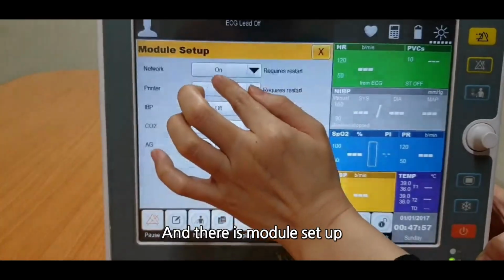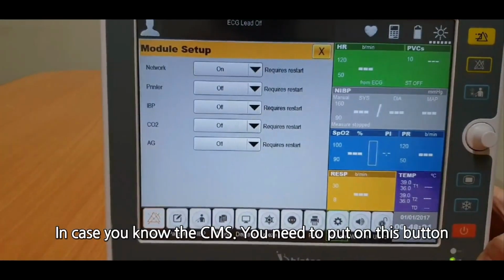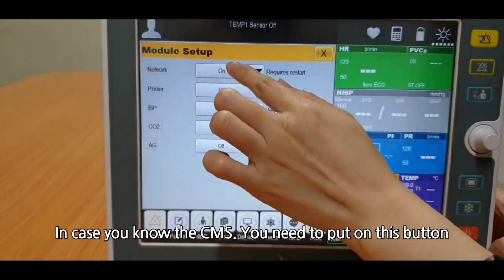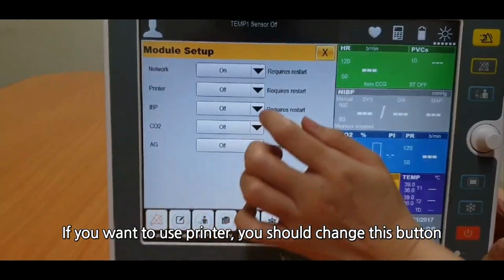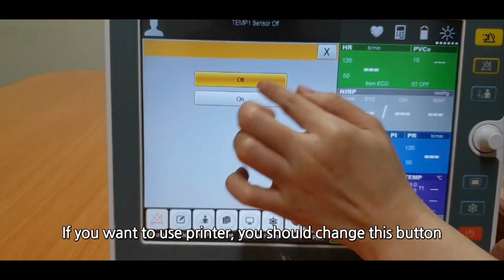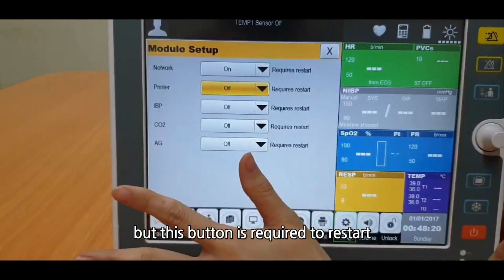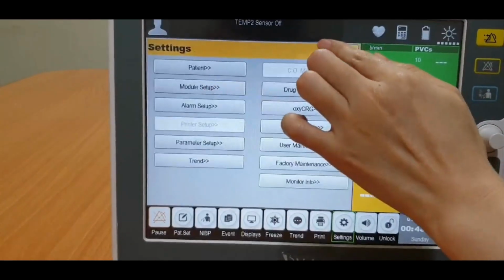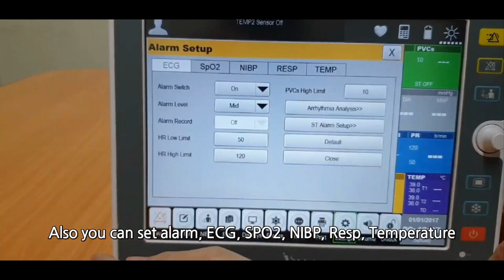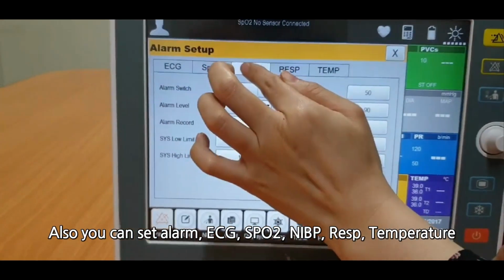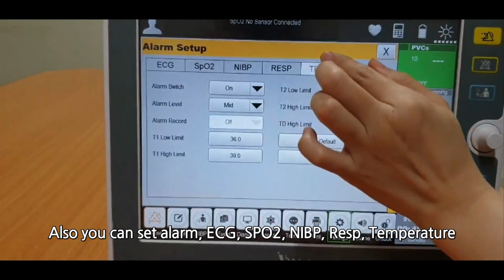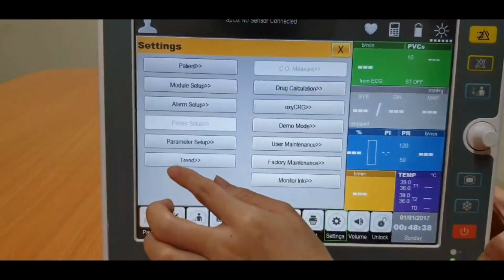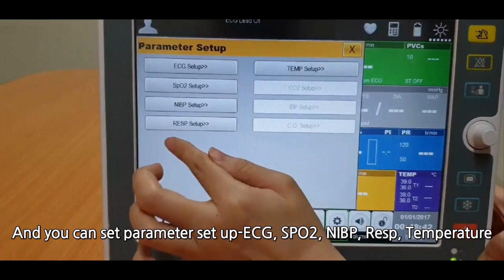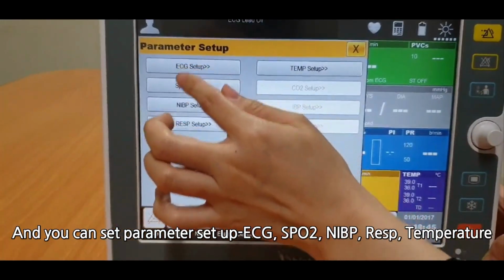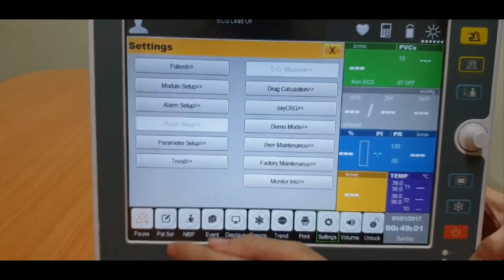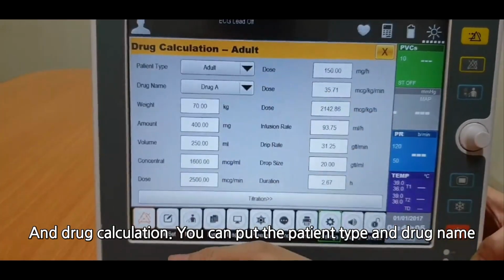And there is module setup. In case you use the CMS, you need to turn on this button. And if you want to use the printer, you should change this button. But this button requires a restart. Also, you can set the alarm: ECG, SpO2, NIBP, respiration, and temperature. And you can set parameter setup: ECG, SpO2, NIBP, respiration, temperature, and drug calculation. You can put in the patient type and drug name.